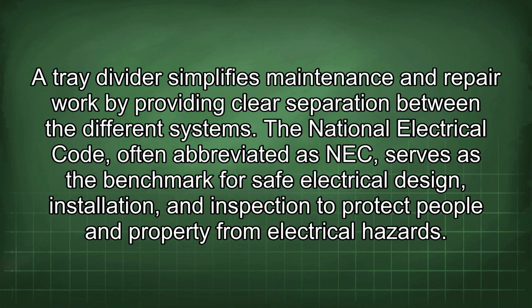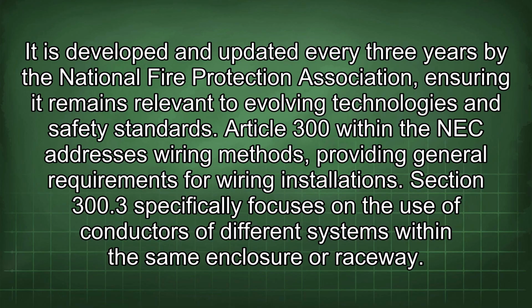The National Electrical Code, often abbreviated as NEC, serves as the benchmark for safe electrical design, installation, and inspection to protect people and property from electrical hazards. It is developed and updated every 3 years by the National Fire Protection Association, ensuring it remains relevant to evolving technologies and safety standards. Article 300 within the NEC addresses wiring methods, providing general requirements for wiring installations. Section 300.3 specifically focuses on the use of conductors of different systems within the same enclosure or raceway.